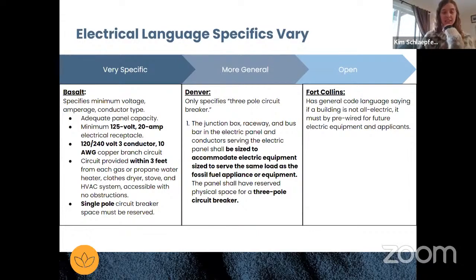Yes, that makes sense, and yes the answer is yes. Any gas-fired combustion equipment would need to be pre-wired, with panel capacity and all elements ready for future electrification. Denver's language requires the panel to be sized adequately to accommodate whatever is going to be converted. It specifies the junction box, raceway, and bus bar in the electric panel, and the conductors serving the panel, all need to be sized to accommodate the electric equipment serving the same load as the fossil fuel equipment.